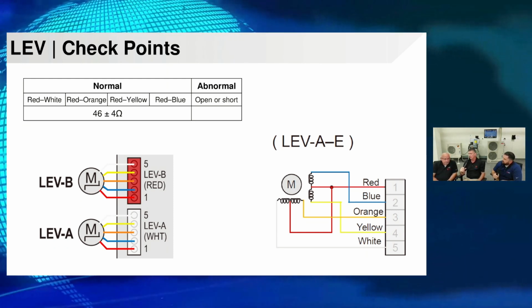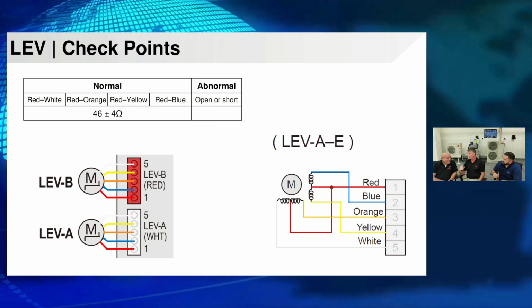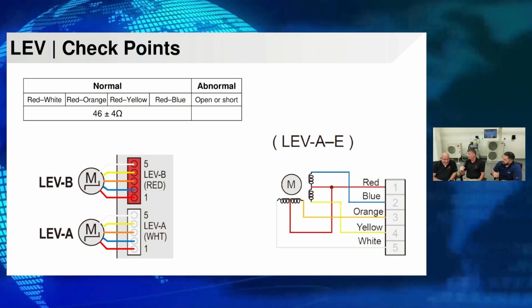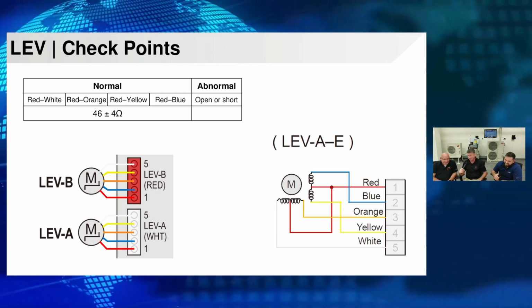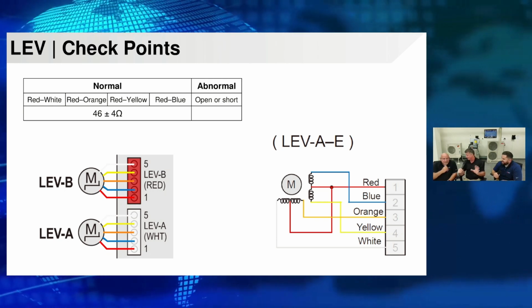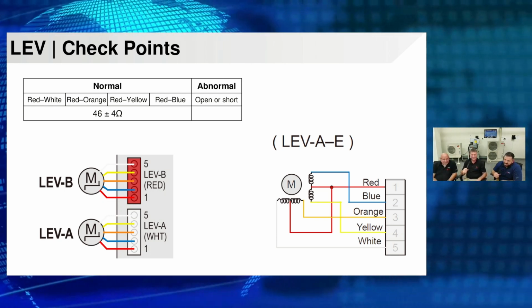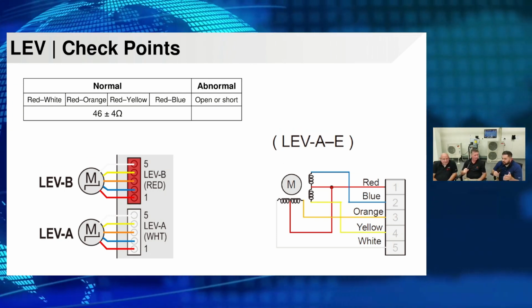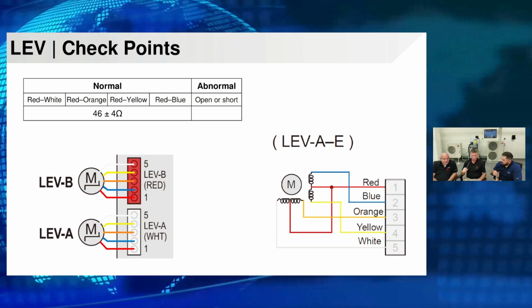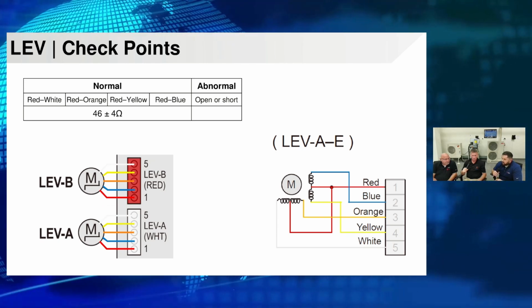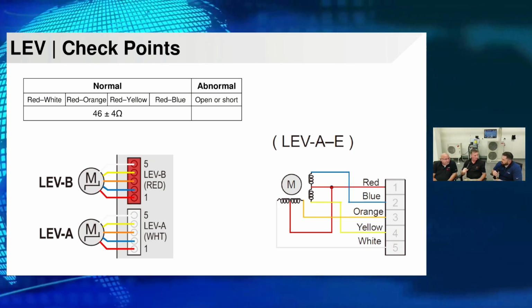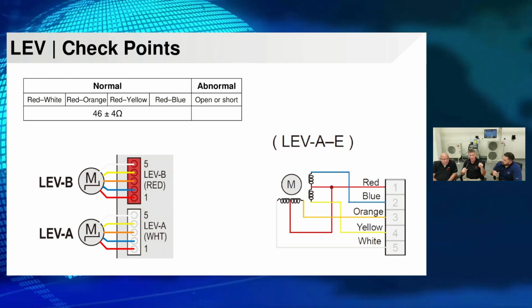What is the best superheat? Slightly above zero. At the very least, we have to be above zero. We can't get that liquid back to the compressor. No compressor likes liquid refrigerant. And then if we're suspecting an electrical issue with the actual solenoid itself, we're just going to ohm it out. And typically on our residential side, we're looking for 46 ohms plus or minus, from common to each one leg.